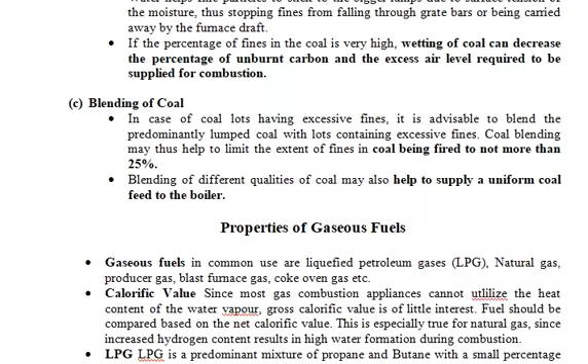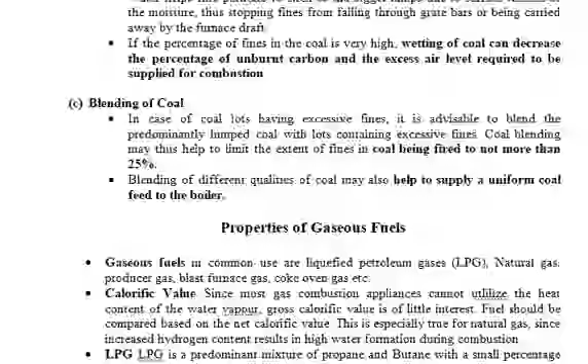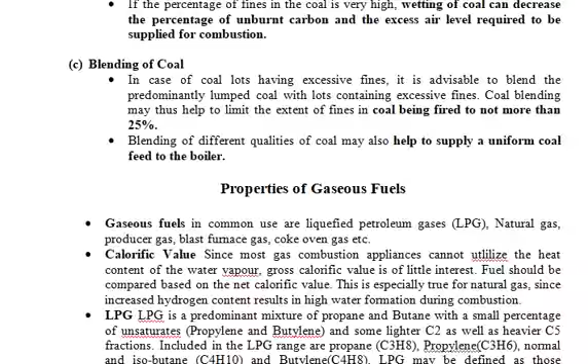It is very important because the conditioning of coal has to be checked before entering the boiler section, the furnace section. Then the next parameter is blending of coal. In case of coal lots having excessive fines, it is advisable to blend the predominantly lump coal with the lots containing excessive fines. Coal blending may thus help to limit the fines in coal being fired to not more than 25%. This is very important. It also helps to supply uniform coal feed to the boiler. The blending of different qualities of coal may also help to supply a uniform coal feed to the boiler.